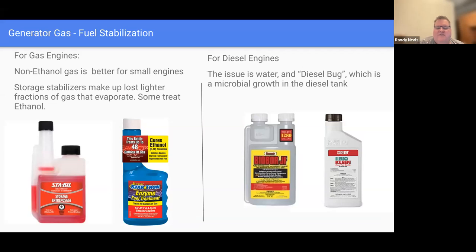One leading cause of diesel generator failure in commercial businesses is a mass of diesel bug, a microbial growth in the tank. When you start the generator, it runs for a few minutes, then a glob of this growth passes through the line, plugs the filters, and the generator stops. If a generator isn't properly maintained, this typically builds up over 3 to 5 years and makes it unreliable when you need it.